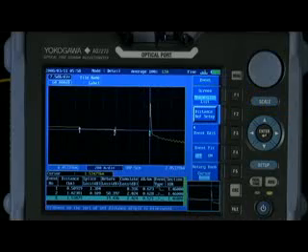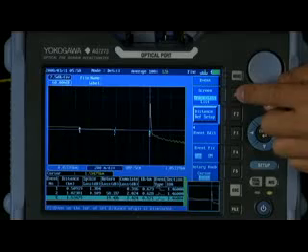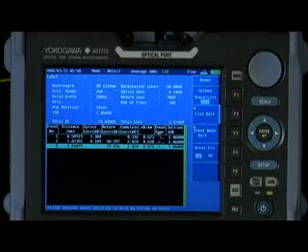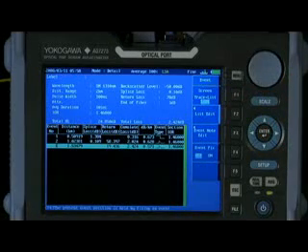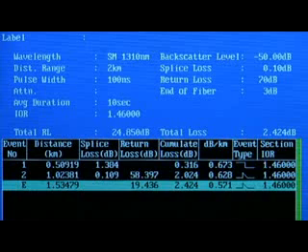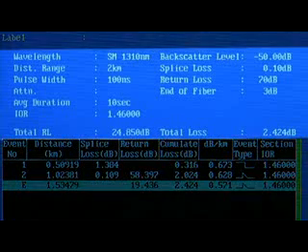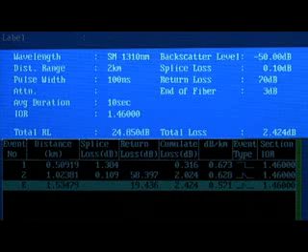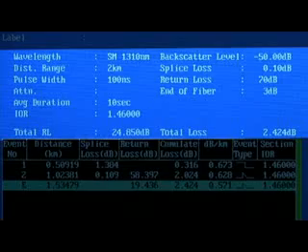An event table is automatically created related to the trace just taken. Along with the event table is the measurement setup, indicating wavelength, pulse width, and other key conditions of the measurement.